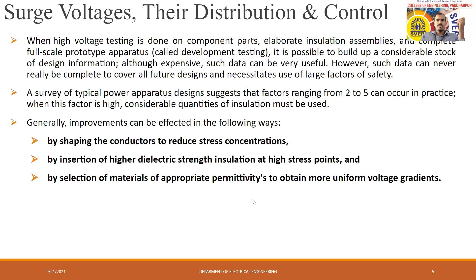Whatever factors should be considered must be used for improvement, like shaping the conductors to reduce stress concentrations, which is an important improvement to avoid or control surge voltages. Another method is insertion of high dielectric strength insulation at high stress points, and another is selection of materials with appropriate permittivities to obtain a more uniform voltage gradient. All these things are important to understand how to control surge voltages.